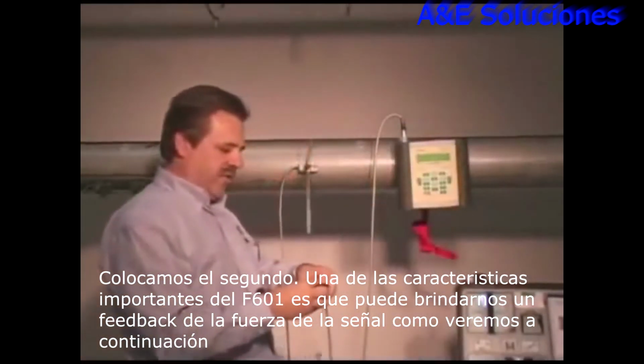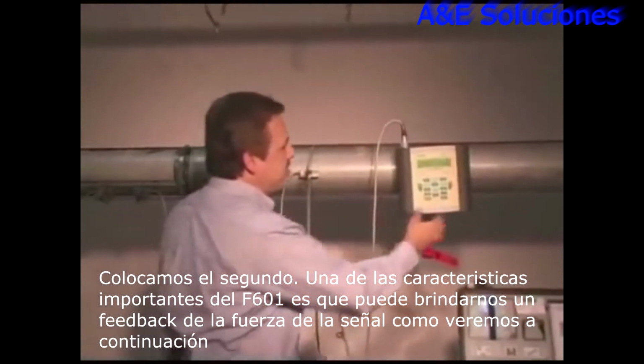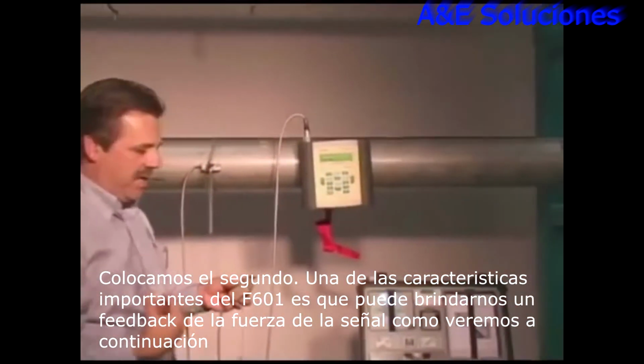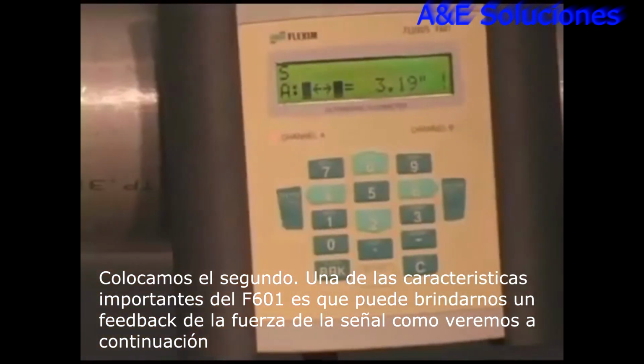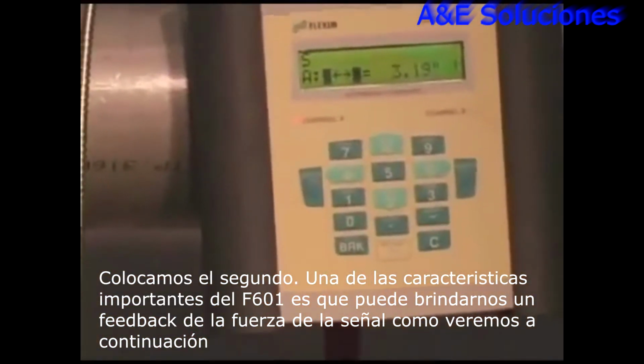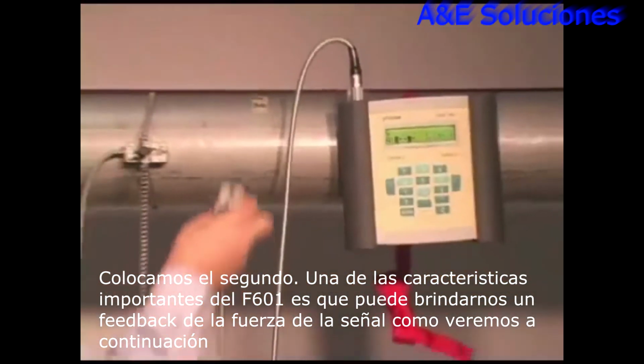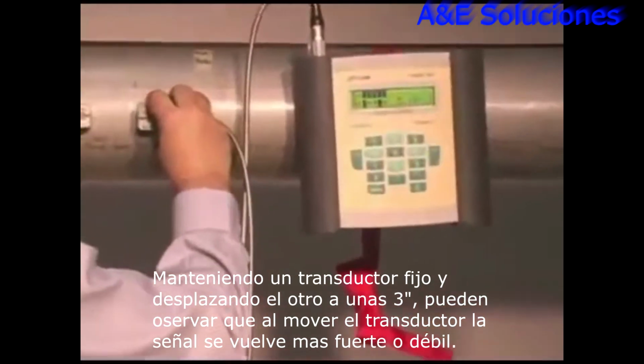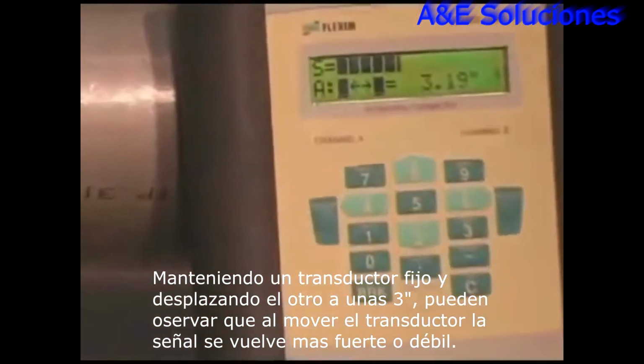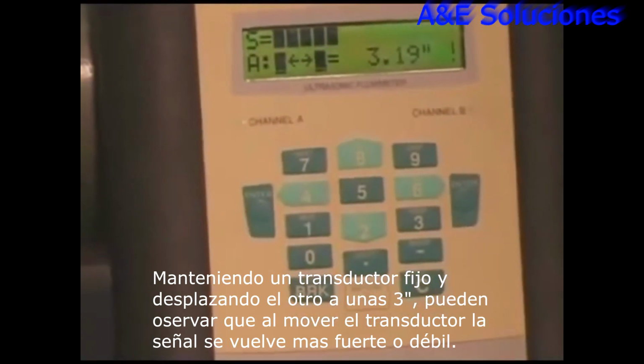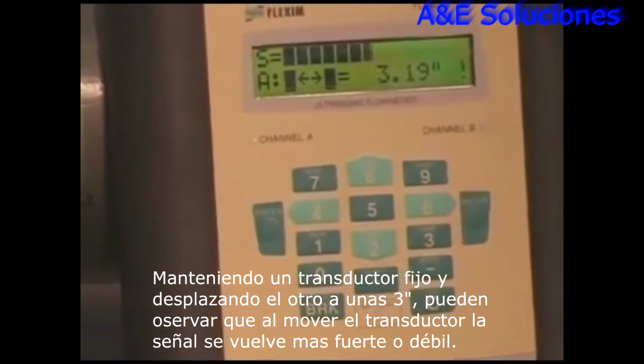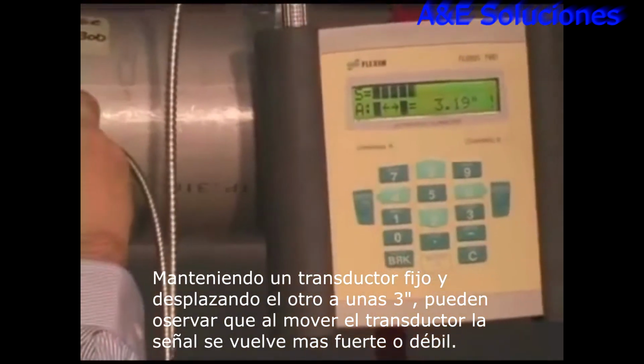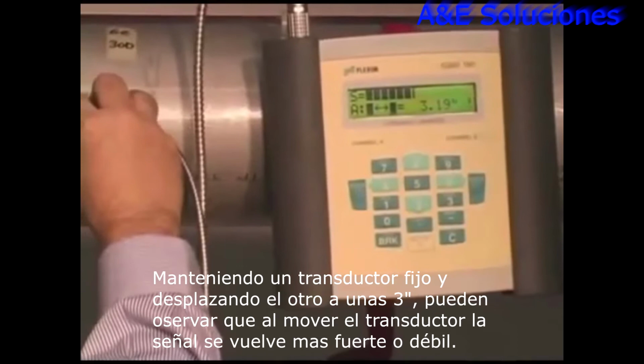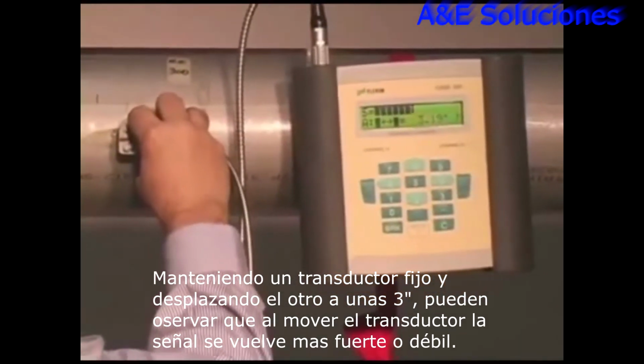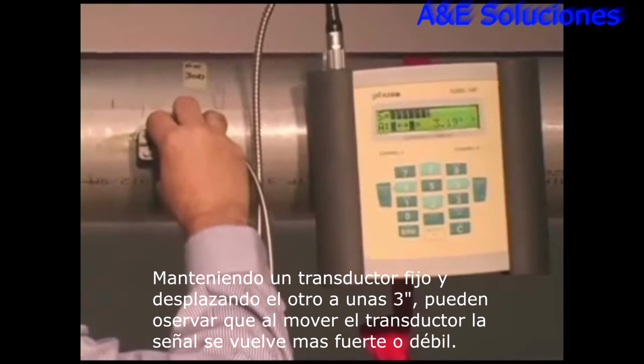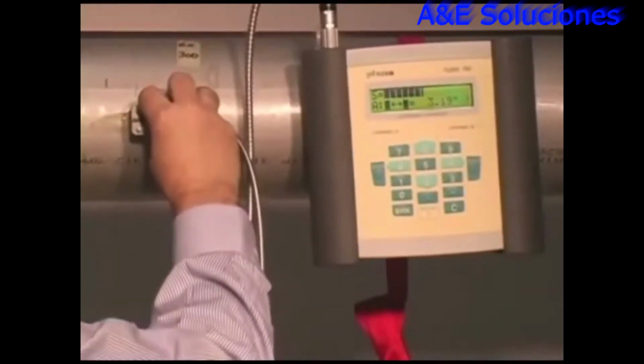Now, at this point, we can move to our signal screen. One of the nice features of this meter is that it gives us immediate feedback on the signal strength. You'll see that I can just hold this transducer to the pipe at approximately 3 inches, and you'll start to see the signal on the display. Want to zoom in on that? There you go. And if I move the transducer around a little bit, I can see some varying amounts of signal. And probably where I'm seeing the highest signal is going to be where I wind up at the 3-inch point. And once I get the chain on, I'll measure it out with the tape measure.